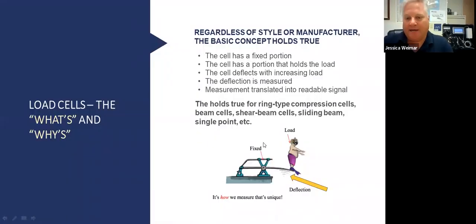You'll see here that as that load changes, the actual frame member of the beam bends, and as it bends, we measure that deflection. That deflection gets measured and then is translated into an electrical signal that can be read by some sort of measuring unit to translate into a weight measurement. It's important to understand that this is true whether it's a compression style load cell, a beam style load cell, sliding beam, shear beam, single point, it's always the same. What's different between styles of cells is how we measure that deflection. This is always the same, it's how we measure it that's different.